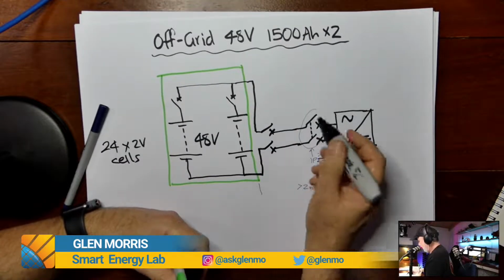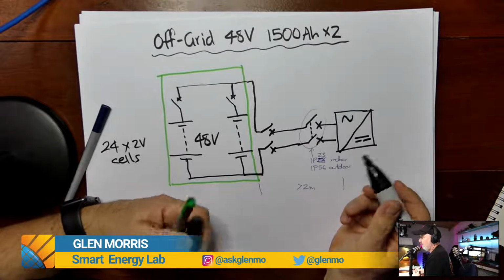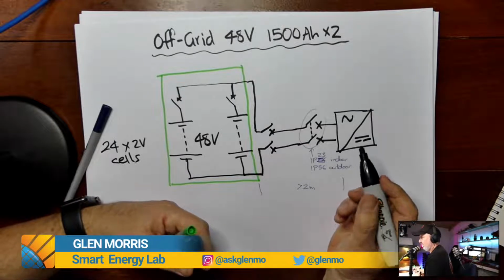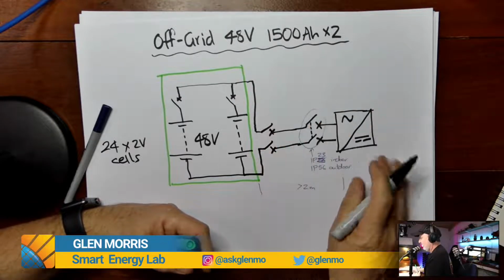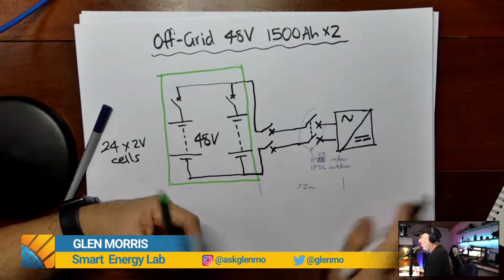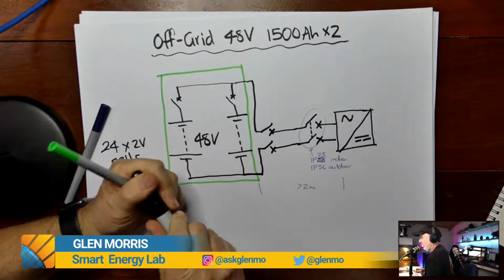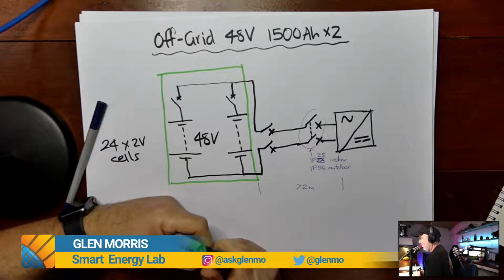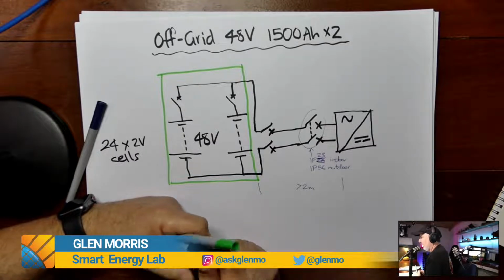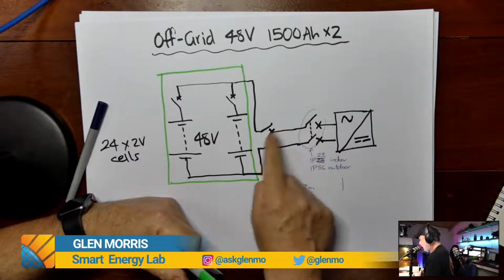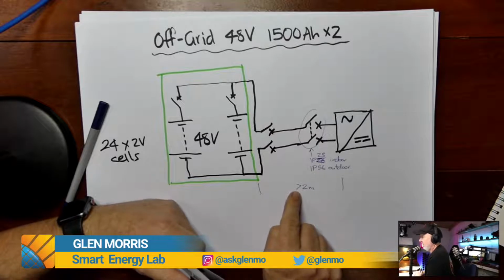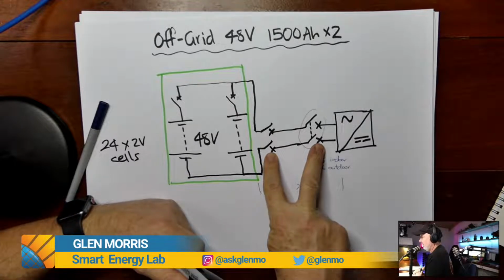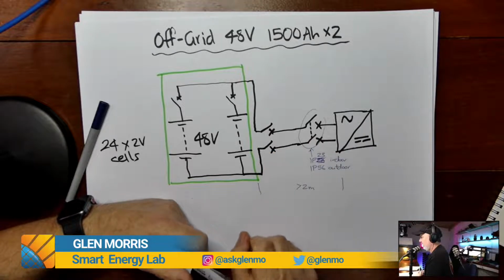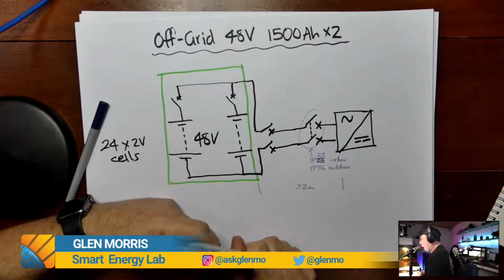Now, one way of avoiding having to put in two probably identical circuit breakers is to bring the PCE closer to the battery system, so it's at most 2 meters away. Now, with large systems, that can be impractical because of the size of the bank and the run of your cables. So you may need to have two. So the key thing is, if it's greater than 2 meters, you're going to need, within 2 meters of the PCE and 2 meters of the battery system, an isolation device.